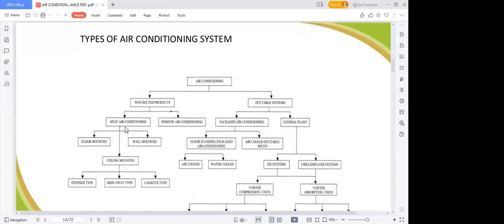One of my friends recently came from the US, they installed a new AC they just bought. After they energized the AC, he was surprised that after some few minutes, the AC worked. After about 1 or 2 hours, the AC dropped. What causes it? The person that was tying the copper pipe to the outdoor unit did not do a proper job. So most of the refrigerant gas leaked away from the system. So you must be careful. Assuming it was a window unit, you will never have such a problem with it. So with split units, you must get an experienced person to do your installation.